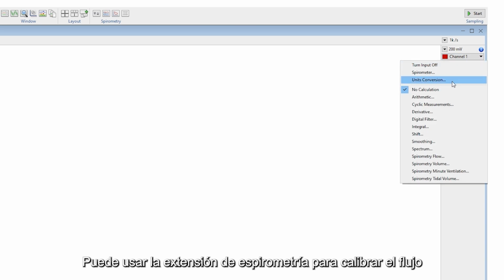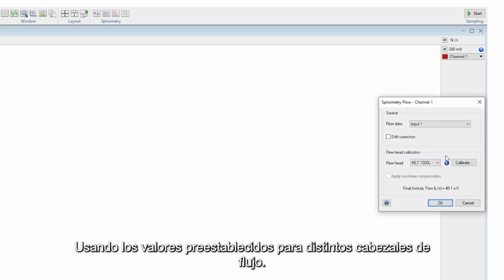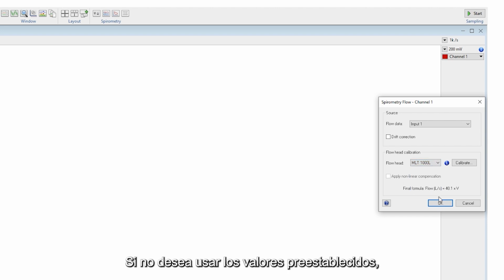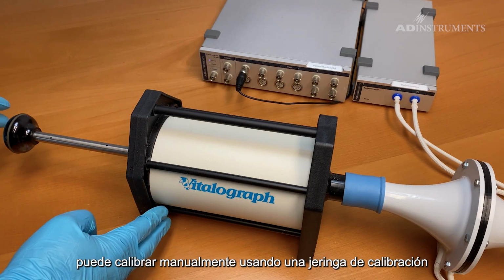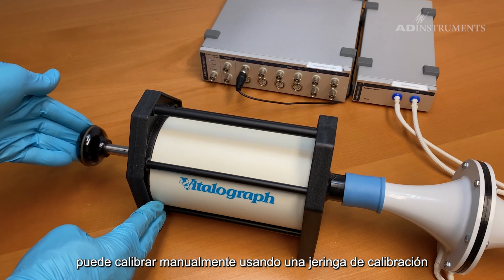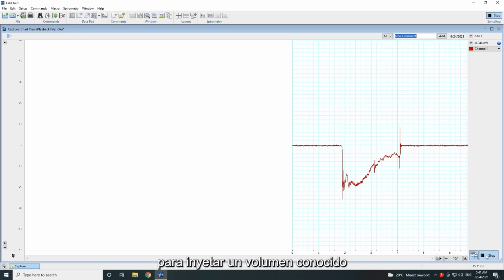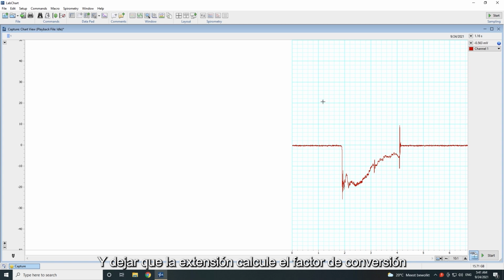You can use the spirometry extension to calibrate flow by using the preset values for various flow heads. If you do not want to use the preset value, you can calibrate manually using a calibration syringe to inject a known volume and have the extension calculate the conversion factor.